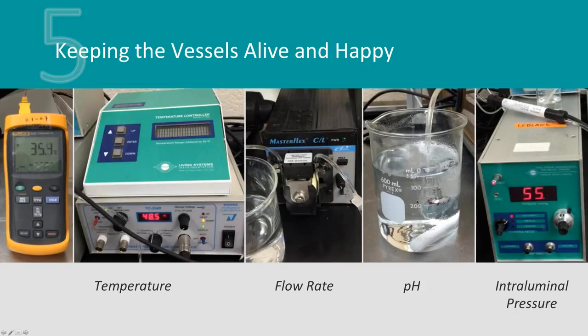to make sure that these bicarb buffers stay at a pH of about 7.4. If you're having trouble with contractility, especially if you get a lot of basal motion artifacts in your blood vessels, it's probably a pH issue. So you'll want to monitor the pH and ensure that it is correct. But actually, your blood vessel is your best pH sensor that you can have in the system, because if the vessel is behaving properly, your pH is appropriate.